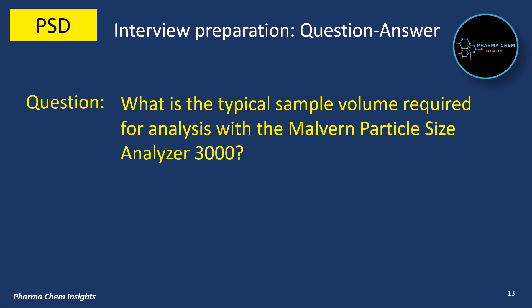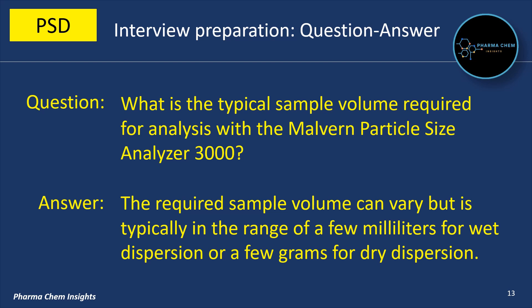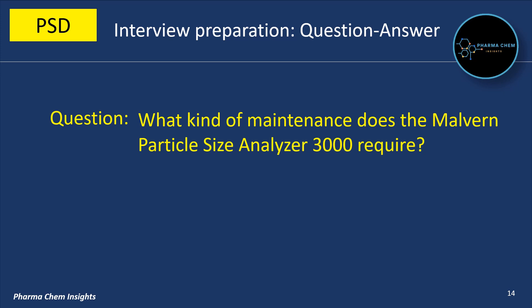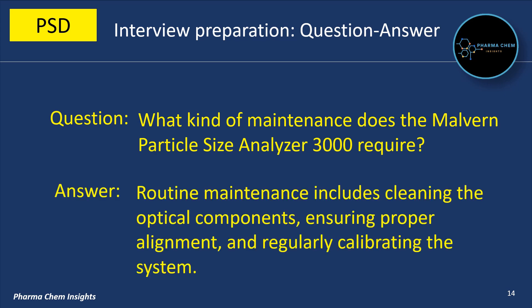What is the typical sample volume required for analysis? The required sample volume can vary but is typically in the range of a few milliliters for wet dispersion or a few grams for dry dispersion. What kind of maintenance does it require? Routine maintenance includes cleaning the optical components, ensuring proper alignment, and regularly calibrating the system.